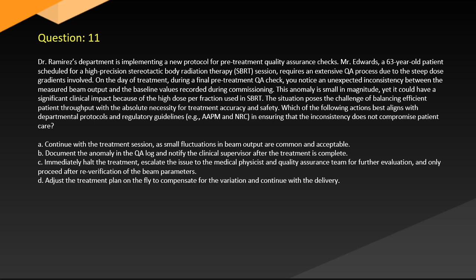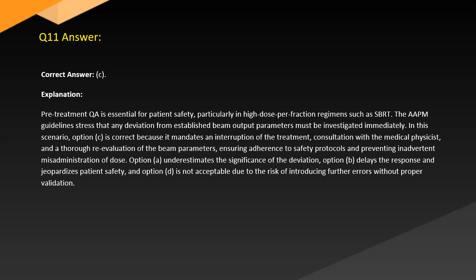Answer. Correct answer, C. Explanation. Pre-treatment QA is essential for patient safety, particularly in high-dose per fraction regimens such as SBRT. The AAPM guidelines stress that any deviation from established beam output parameters must be investigated immediately. In this scenario, option C is correct because it mandates an interruption of the treatment, consultation with the medical physicist, and thorough re-evaluation of the beam parameters in adherence to safety protocols, preventing inadvertent misadministration of dose. Option A underestimates the significance of the deviation. Option B delays the response and jeopardizes patient safety. And option D is not acceptable due to the risk of introducing further errors without proper validation.